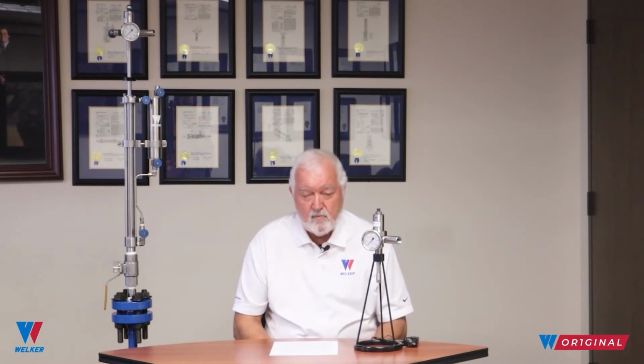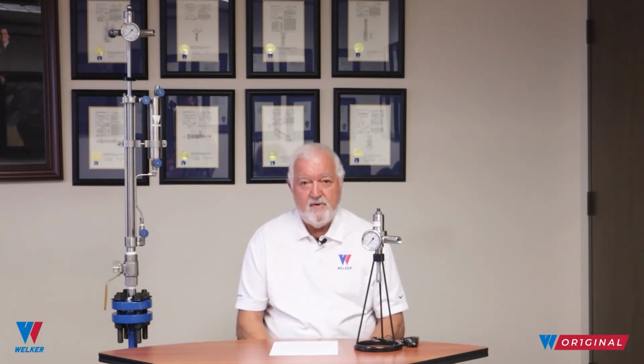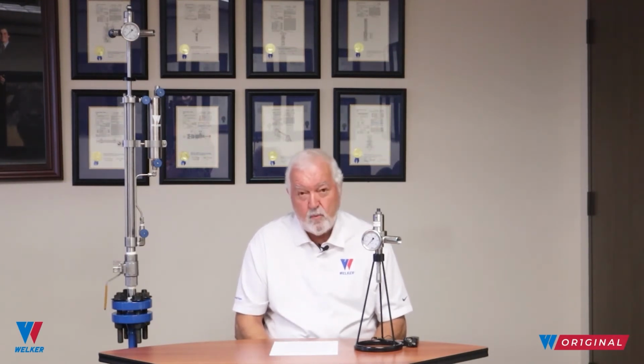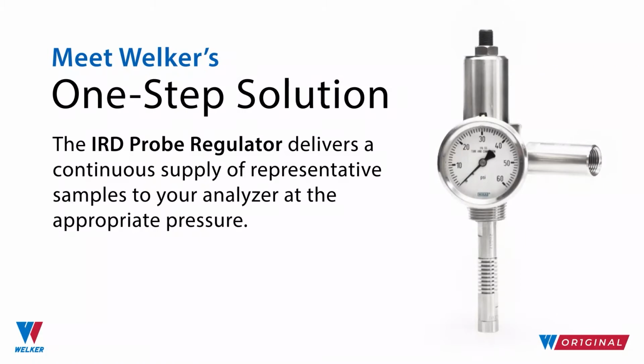R.H. Bob Welker of Welker and Charles Drake of Natural Gas Pipeline Company of America began to develop a probe regulator that would revolutionize the online gas chromatograph and gas quality measurement industry forever. The idea of taking a pressure cut in the pipeline and letting the warm pipeline gas offset and mitigate the Joule-Thomson effect was something that had never been done before. It seemed like a reasonable approach to get away from the multi-stage regulation going on at the time, using one regulator rather than three or four to accomplish the pressure cut needed to get into the analyzer.